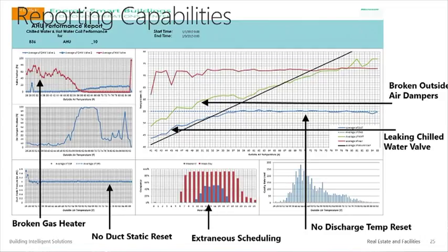I should never have to cool. If you know what a duct static strategy is, we don't have one. That straight line on that bottom left, that's bad. This isn't a lab building, so it shouldn't be running on weekends. So red is weekday, blue is weekends, and it turned out it was running on Sunday. Any mechanical engineer can look at these data points and in 10 seconds say, yeah, you have some problems. Typically, we just didn't have the time to go through.